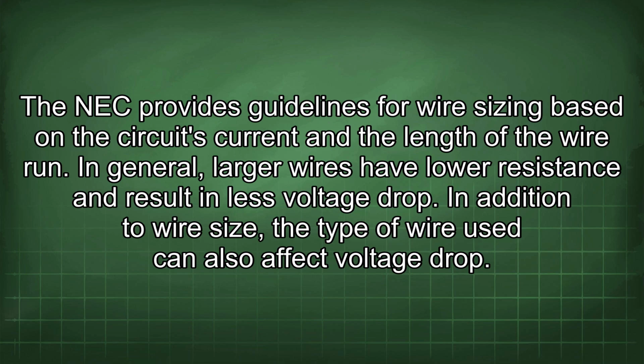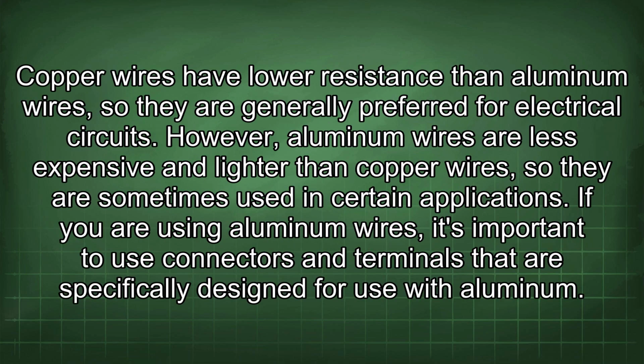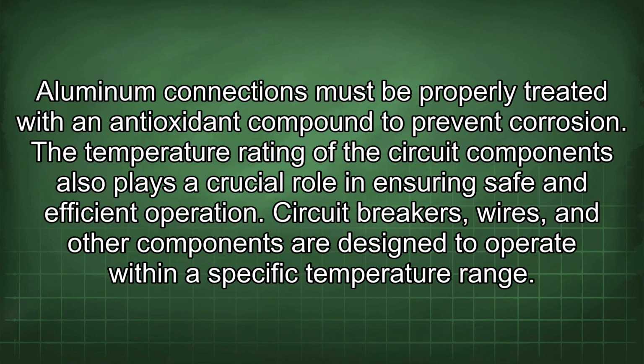In addition to wire size, the type of wire used can also affect voltage drop. Copper wires have lower resistance than aluminum wires, so they are generally preferred for electrical circuits. However, aluminum wires are less expensive and lighter than copper wires, so they are sometimes used in certain applications. If you are using aluminum wires, it's important to use connectors and terminals that are specifically designed for use with aluminum. Aluminum connections must be properly treated with an antioxidant compound to prevent corrosion.